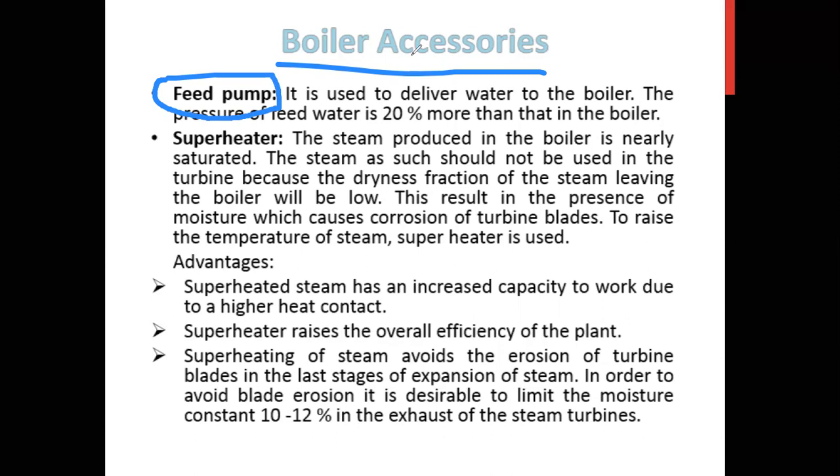That's why the feed pump is used. It is used to deliver water to the boiler, and the pressure of the feed pump is 20% more than that in the boiler, because the high pressure is needed to transfer water from the condenser to the boiler. This feed pump is not inside the boiler, but it is connected and it helps the boiler to run properly.